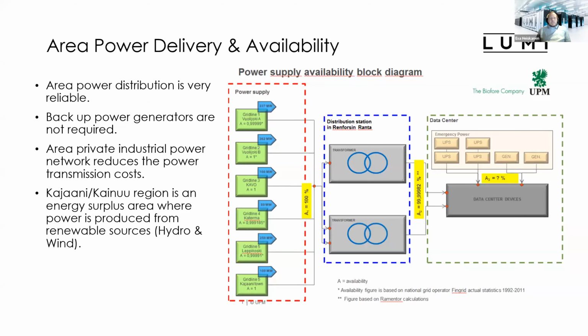So a couple of details about the power distribution of this area. The power distribution of this area is very reliable, and backup power generators are not required. In our case, we haven't implemented them on the national or the Lumi data centers. So there are 6 different directions from the national grid that can feed the area power. And in the area transformers, there is installed capacity of 230 megawatts currently, which is then fed to the data center from 2 different sources. And only the critical components like cooling and storage and management systems are covered with the UPS. So HPC cabinets are running directly from the grid power.